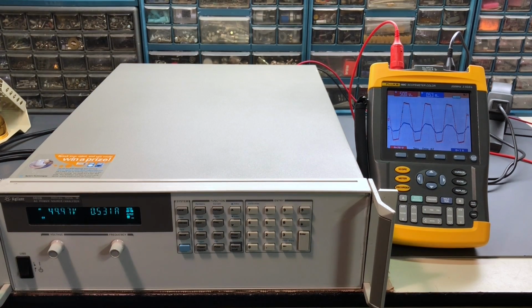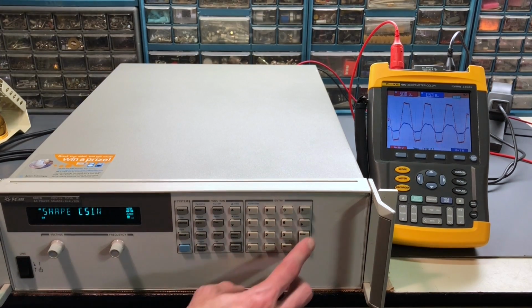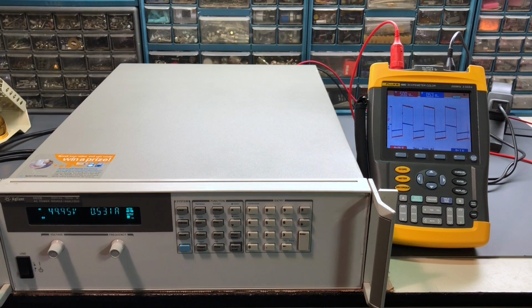It was at 120 for some of the other examples that I was doing. It's set to just 50 volts now. But very distorted looking waveform. You'd have to use that with caution because certain types of loads could be damaged with a very distorted waveform like that. So it has its place for testing, but does need to be used with caution. Go to shape, down to square wave, and we can see a very squared off looking wave there. The blue trace is the current waveform, and you can see it's also very squared off, of course.